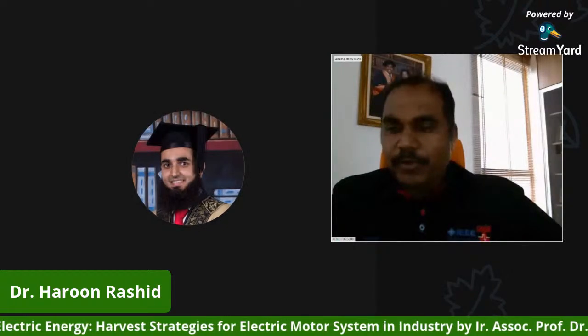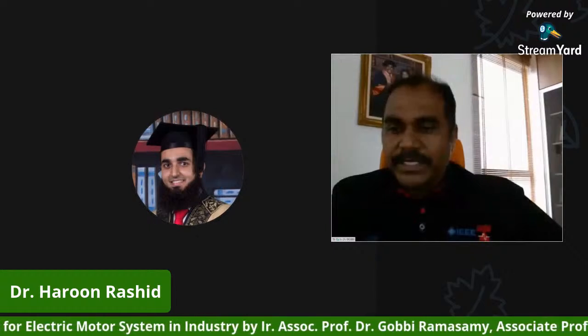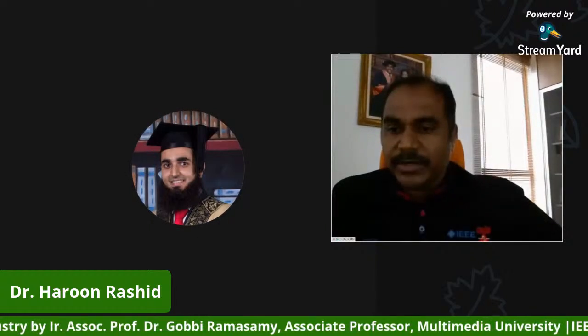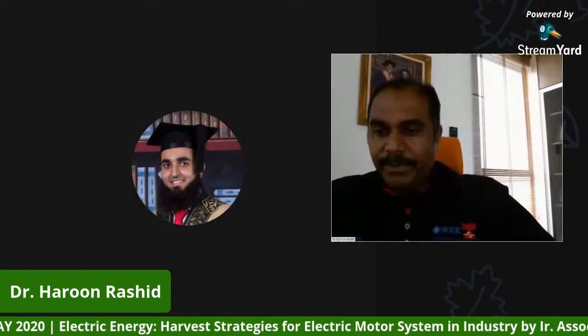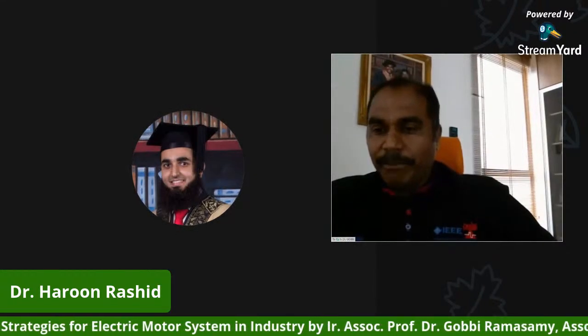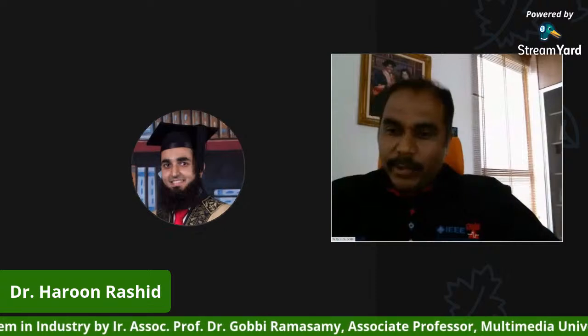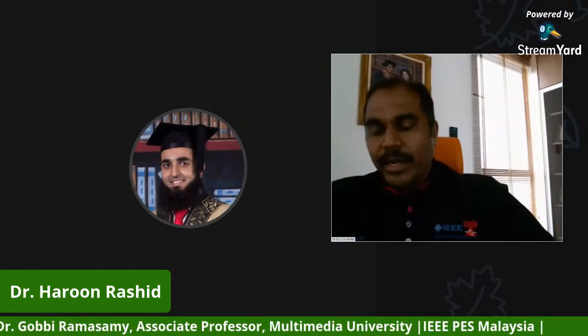Okay. One thing you can do is check the current system. You say the design stage consultant over-designed it. You can check whether it is actually oversized by measuring the power of the motor, the pump system. So what is the power value? Based on the power and the nameplate of the pump, you can find out whether the pump is running at light load or not. If it is light load, then you know it is oversized. It is running without VSD, fine.